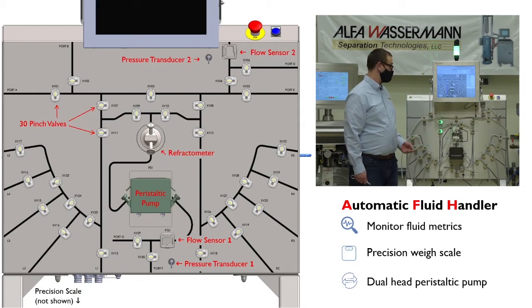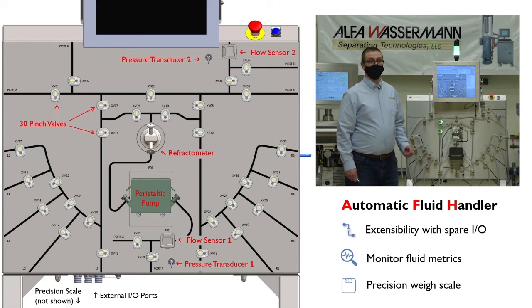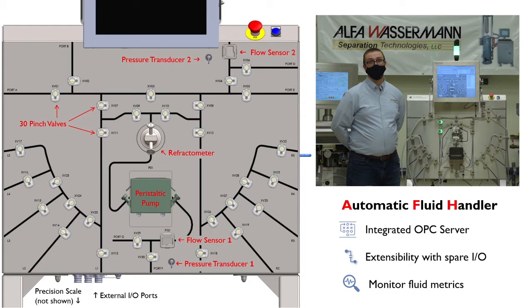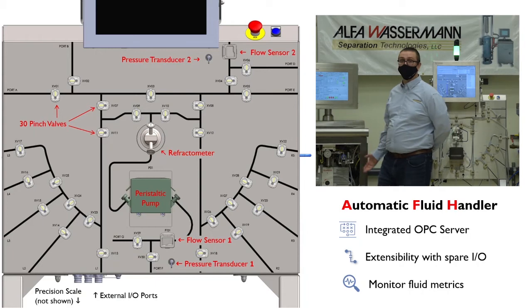The system also comes equipped with some spare I/O ports to easily add any instrumentation that a facility may require. Network integration is also readily available to utilize upstream or downstream inputs and outputs via open-platform communications, or OPC. This means that the system can also monitor and control subcomponents from other systems, such as the rotor speed from an Alfa Wassermann smart console.